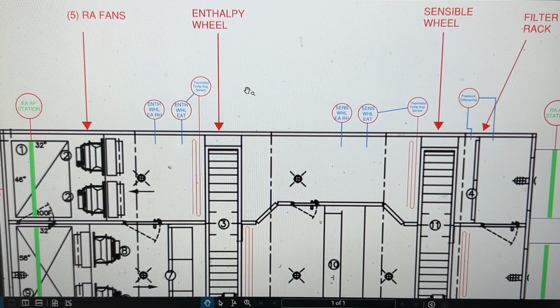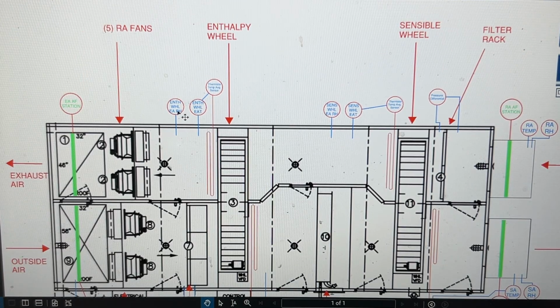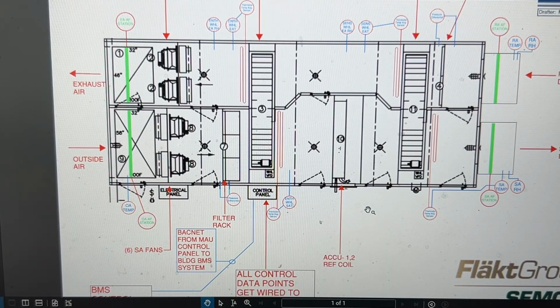Now we pass through the enthalpy wheel with another averaging sensor, which gives us our enthalpy wheel exhaust air temp, and another humidity sensor. And then we've got our fan array here, which is all of our, I think it's 5 return air fans that exhaust it to the outdoors. So all of these points that I have here all communicate back to the control panel on the unit here. So this air handling unit, makeup air unit, comes back to this control panel where it has its own controller.